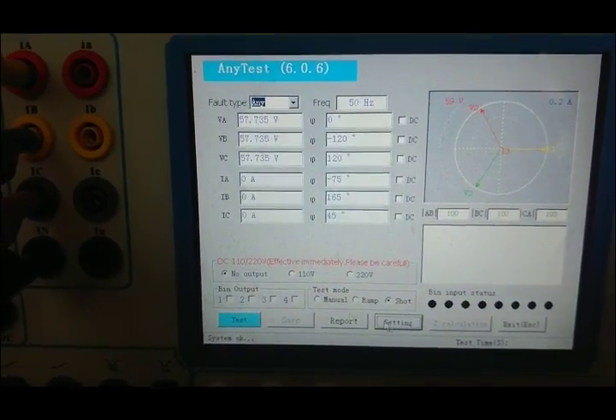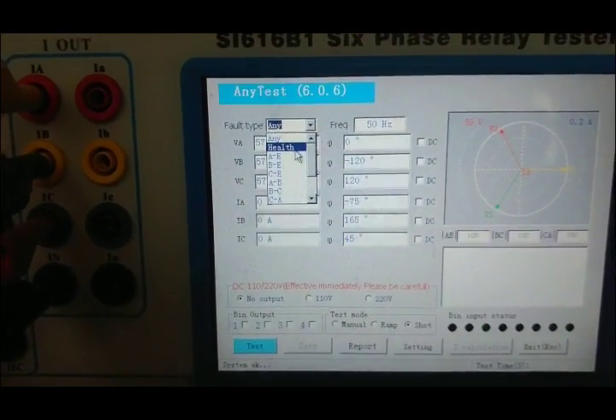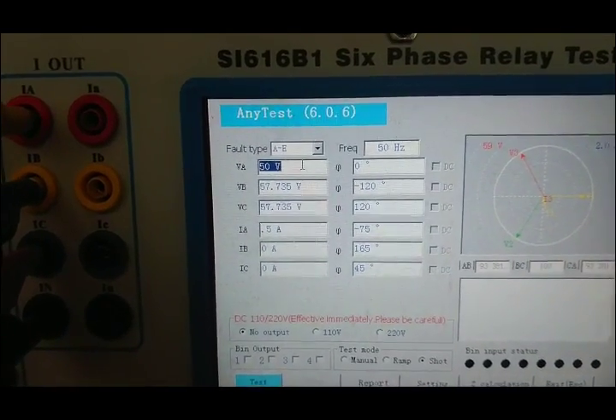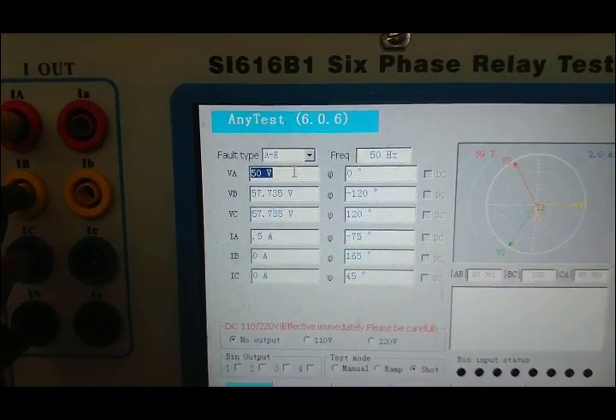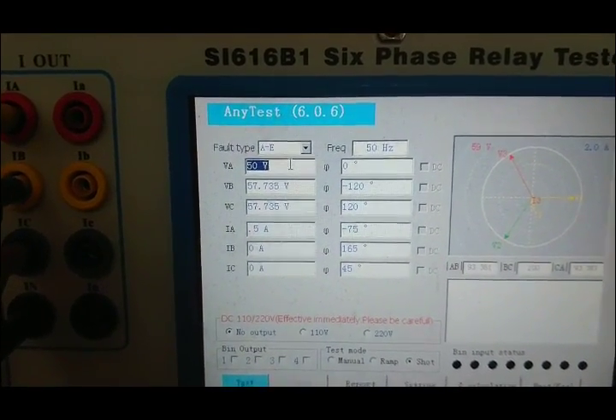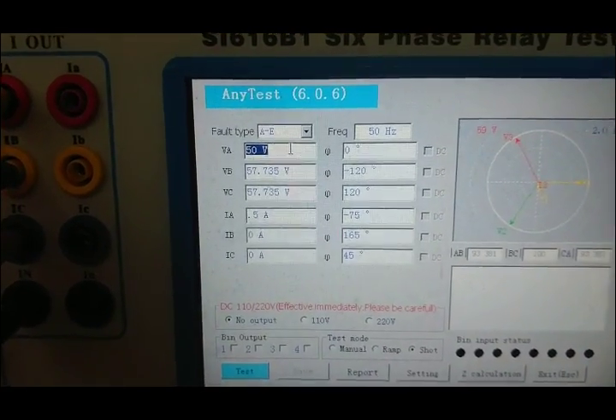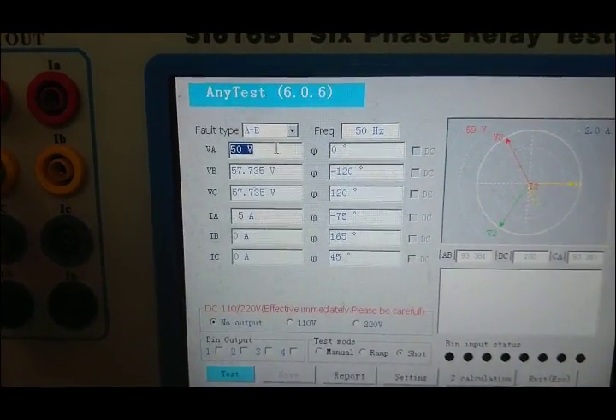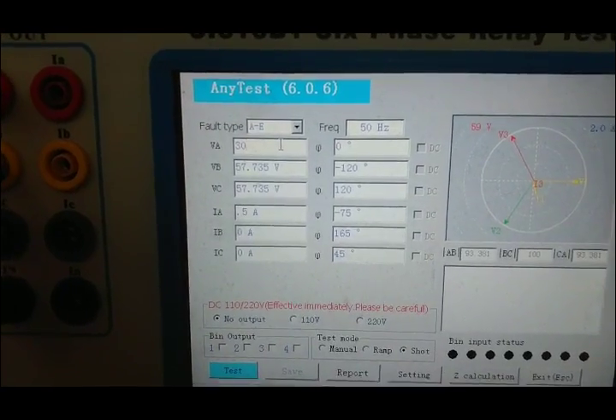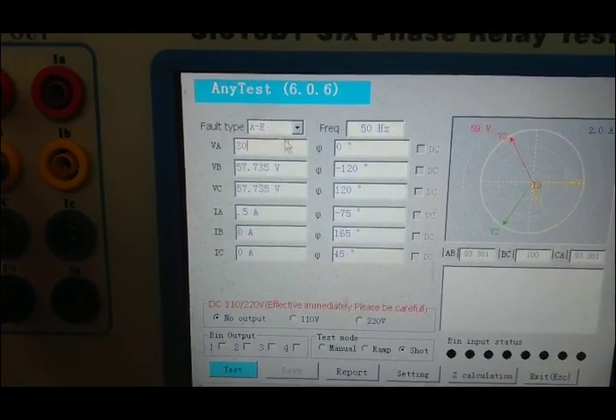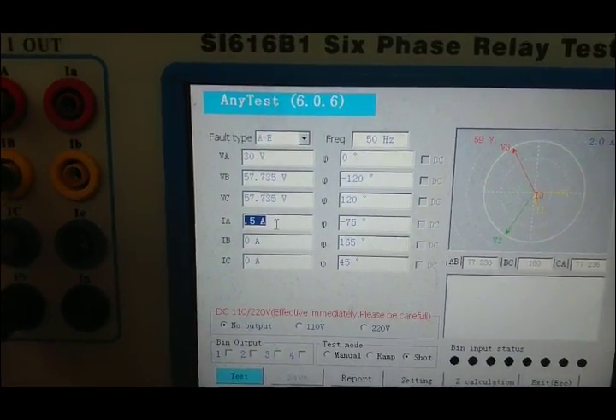Post-fault is usually 0 seconds. Now we simulate single-phase grounding faults. The voltage of A phase is set to 30 volts, which should be smaller than the normal voltage value.